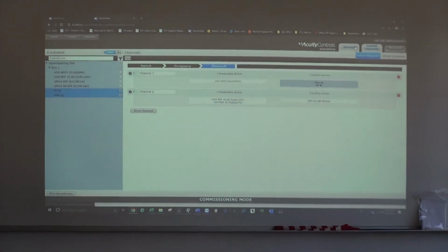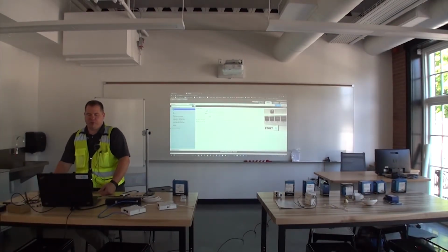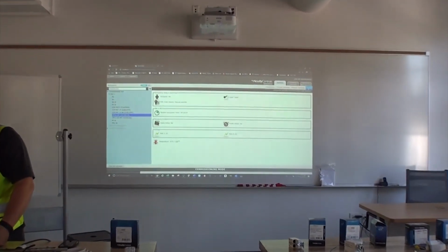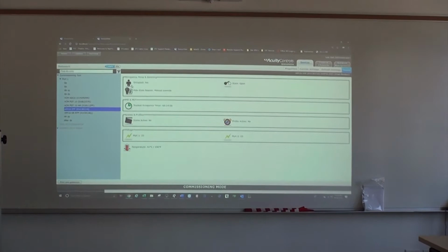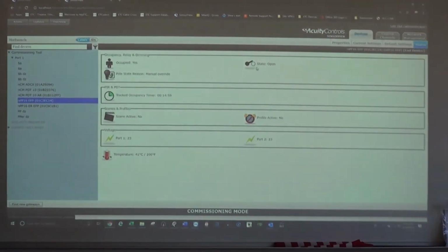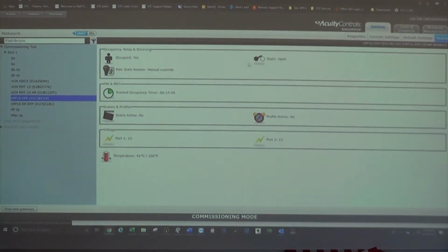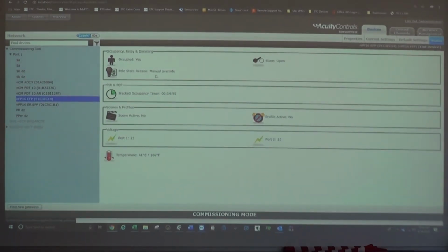So that's the basic control. If you're troubleshooting, you can grab a device, click on status, and see what's going on. You can see that this room is occupied, the state is open, and the reason why the state is open. You'd think if it's occupied it should be on, but it's manually overridden, because I turned the lights off over here. So you can see the state of your room and why your lights are on or off just by going to status.